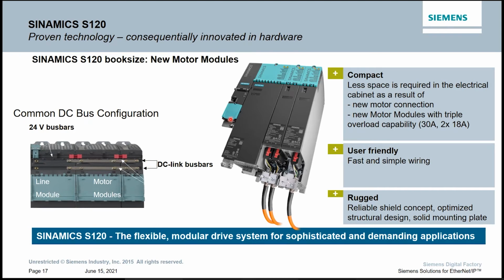And then you have the control unit, which is a very interesting concept. With the microprocessors being so quick, Siemens was able to condense 6 drives into one control unit. So this can operate up to 6 motors. I say 6 drives, but I'll say 6 motors because Siemens has the options of having a dual axis motor module. These dual axis motor modules can run 2 motors independently. One can be in safe torque off, and one can be fully functional. You can pop an IGBT in one of the motor modules. It'll be fully flexible depending on how you run your machine.